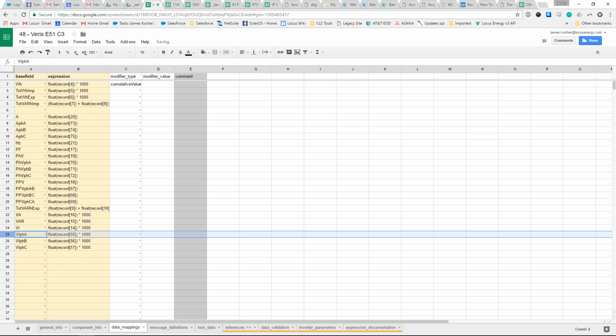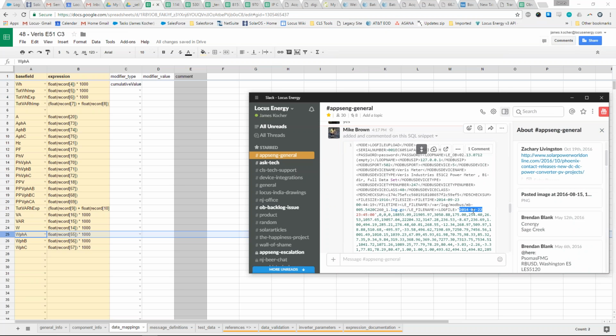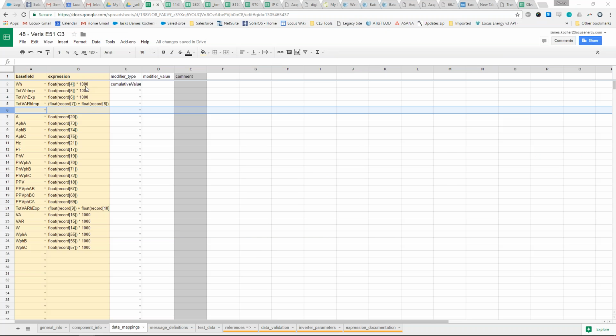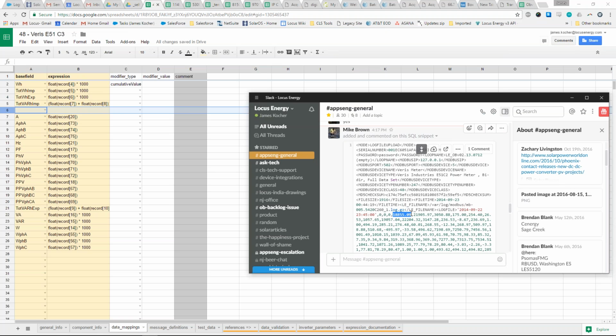All right, so in the first example here, I'm looking at the timestamp. Let me move this up so you guys can see. Okay, so 2014 922, right? I don't think the timestamp actually counts as one, so maybe that's the difference. So let's say 000 are our first 3, and then the fourth one is this 18,855, right? So that's watt hours. Now, there's a little extra piece of the equation here, which is the watt hours are times 1,000 because we deal with watts and not kilowatts. So we take this 18,855 and multiply it by 1,000, and this becomes our watt hours.